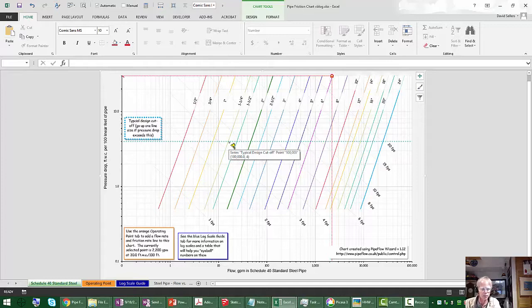You can actually do a life cycle cost based sizing operation, and in process they actually might go for higher friction rates because you aren't so worried about noise, and you may figure, well, I'm going to replace this pipe when my process changes, and so they're not as worried about erosion. But in our industry, we tend to think this building could be around for a really long time. We'd like the pipe to last, so I don't want to erode it by having the velocity too high, and I certainly don't want noise. I don't want to bother people with the sound of water flowing in my pipe. And it turns out that 4 feet per 100, which is this dotted blue line, is a friction rate that'll keep you out of trouble.